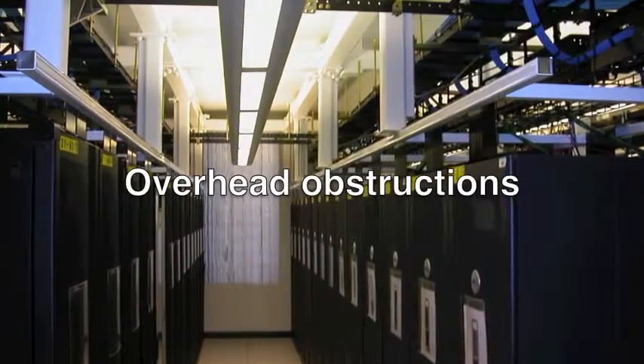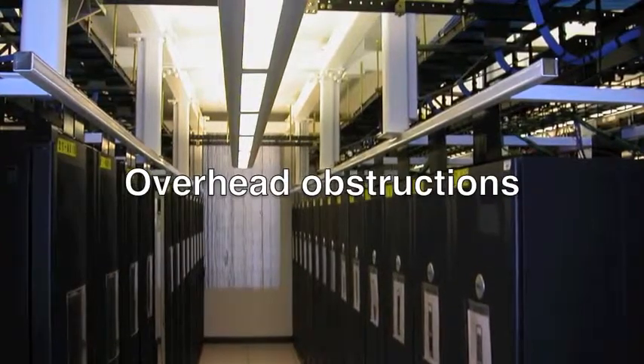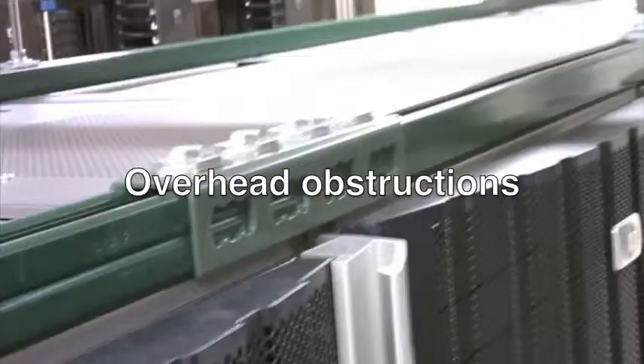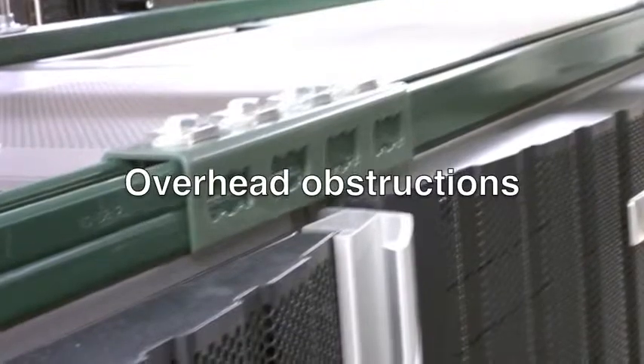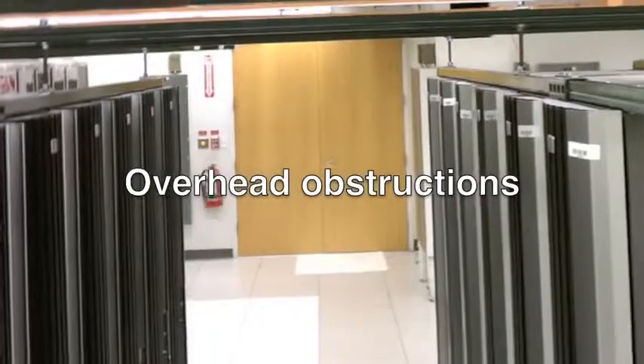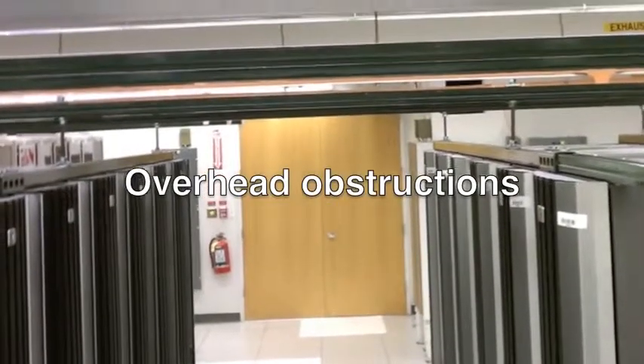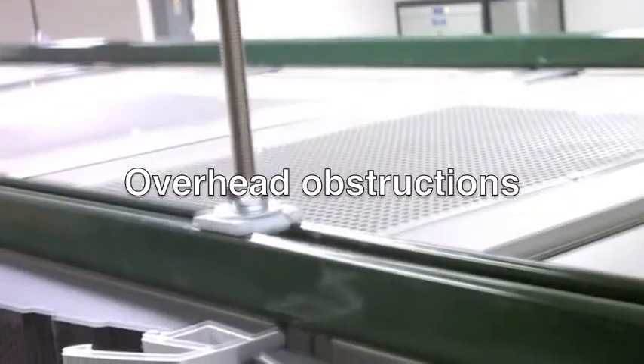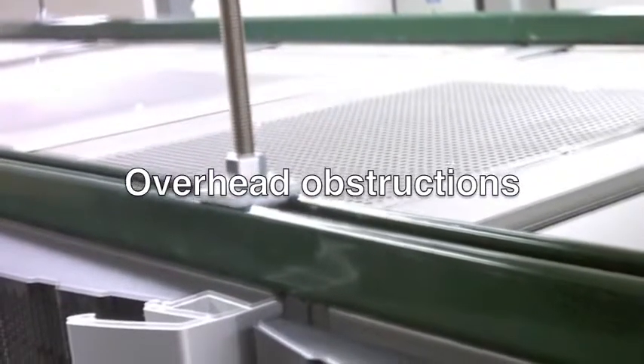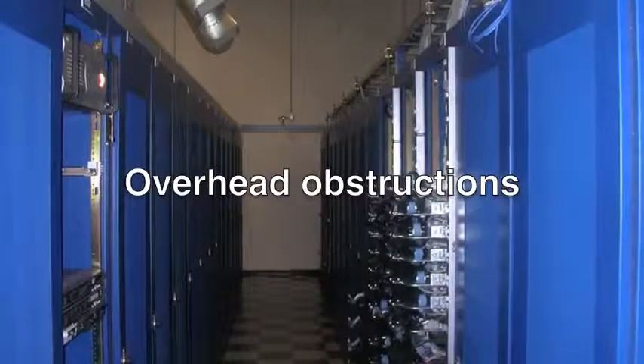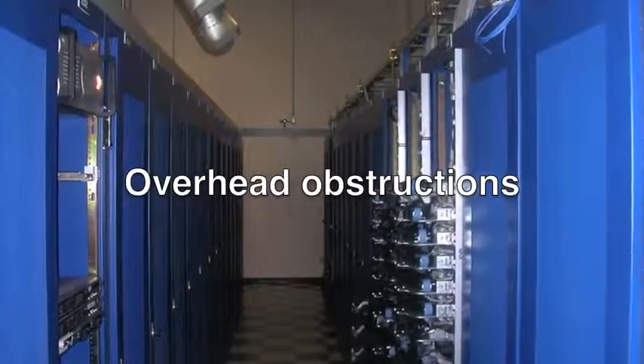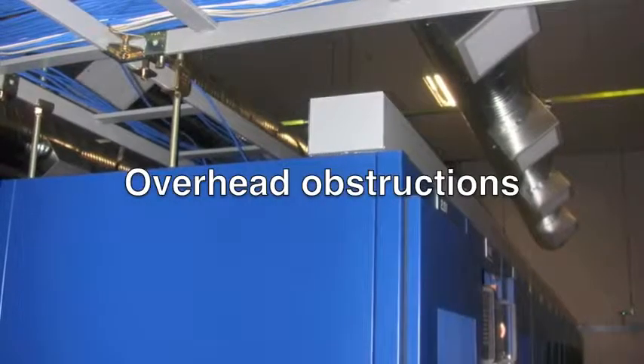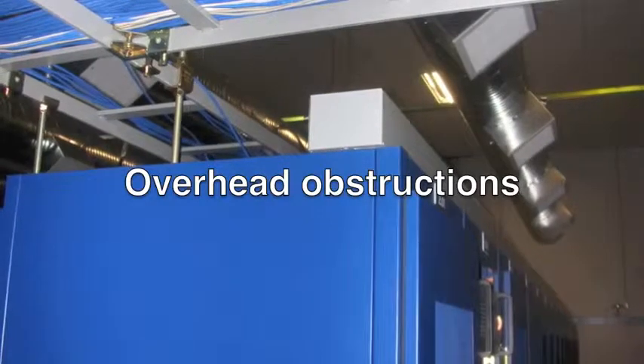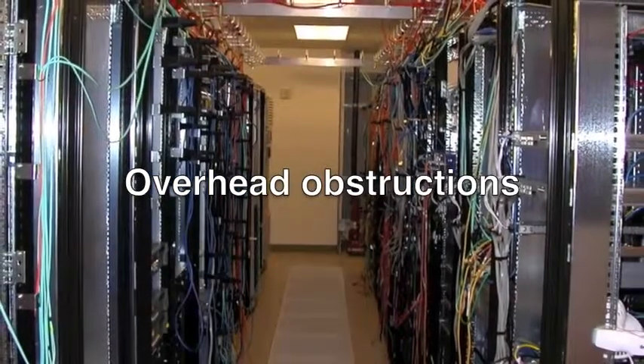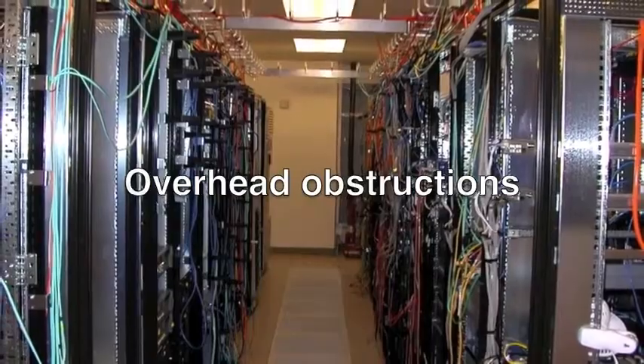These overhead obstructions that you see above the racks are actually earthquake bracing. We often see unistrut laid across the top of racks in order to support cable trays, so that needs to be accommodated. Notice the big brackets on top of the strut, so you can always use that strut as a supporting surface. Here we see on the blue racks overhead cooling and gray power buses on top of the racks, and lastly some overhead cable trays that span across the aisle.